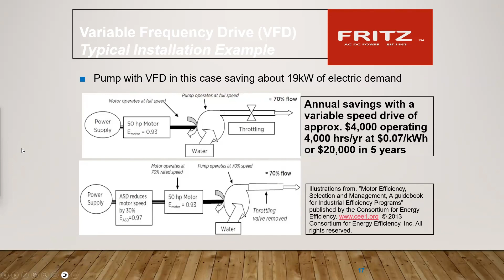There are multiple applications out there that are variable torque loads, where they're the centrifugal fans and blowers, axial fans. Fortunately, my father used to have a manufacturing company that built big centrifugal fans and blowers and axial fans. And so it gave me an insight, really quickly, as I look at things, I can see areas where to do it. A lot of people overlook some of the constant torque load opportunities, but if you have mixing or conveyors or compressors and those things, you can actually slow these down. It's more of a linear horsepower drop, but there are energy savings compared to running it at fixed speeds.